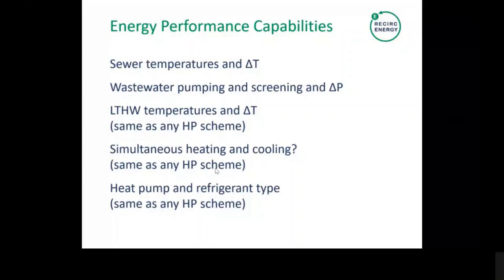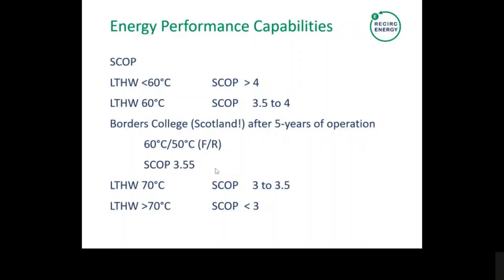Here's a range of performances from real projects or calculations. At Borders College in Scotland - emphasised because it's colder up there in terms of sewer temperatures - we've managed to achieve a seasonal COP of 3.55 over five years, delivering 60-degree low temperature hot water. If you go down in low temperature hot water temperatures, the COP will increase, and if you go up, it'll decrease.